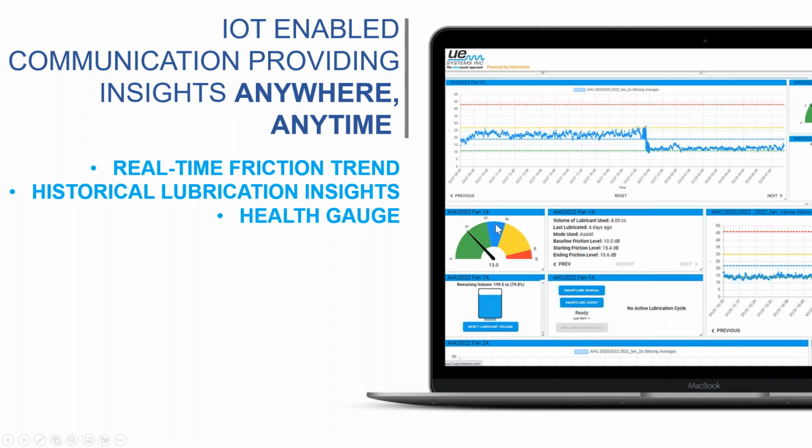So if you can imagine, you start to lubricate, even if you're not using our single point lubricators and you're just using the OnTrack to monitor the friction of the bearing, which you can do, and you start to lubricate that bearing, this arrow starts to fall to the left after every shot of grease that goes in there. Guess when you stop greasing? When it hits 14, right? That's when you stop. I've hit the best possible friction level for that bearing.